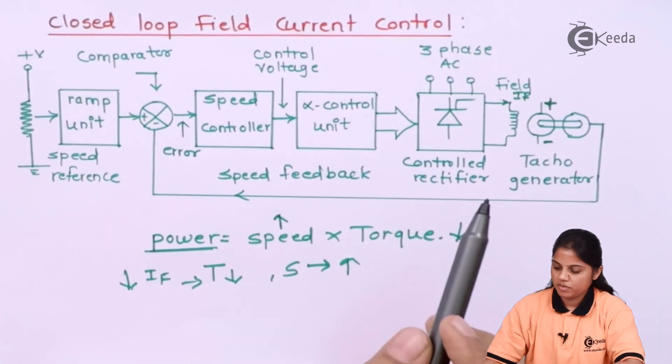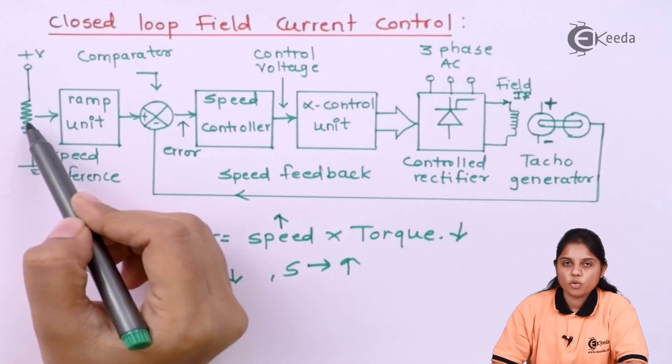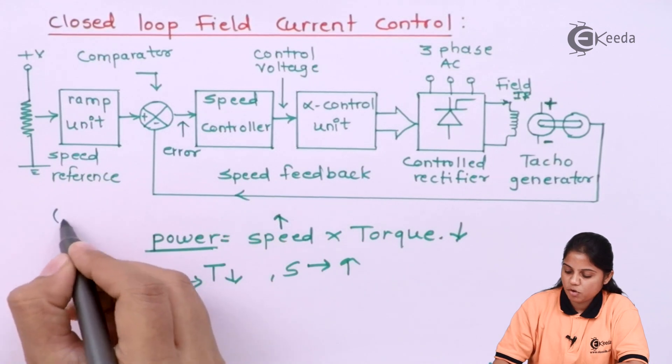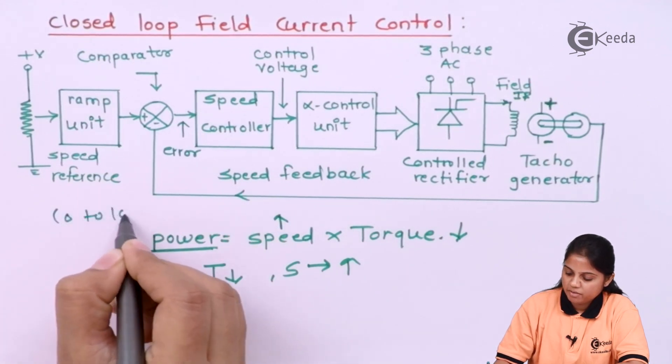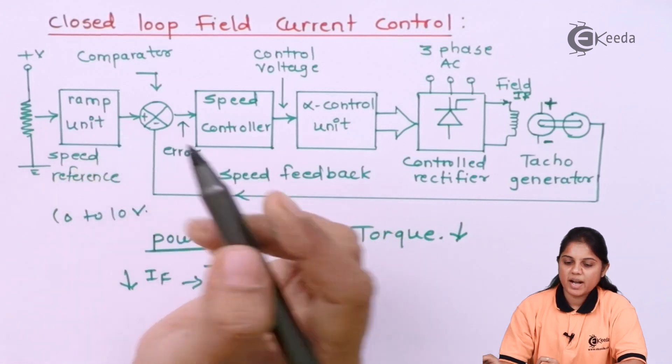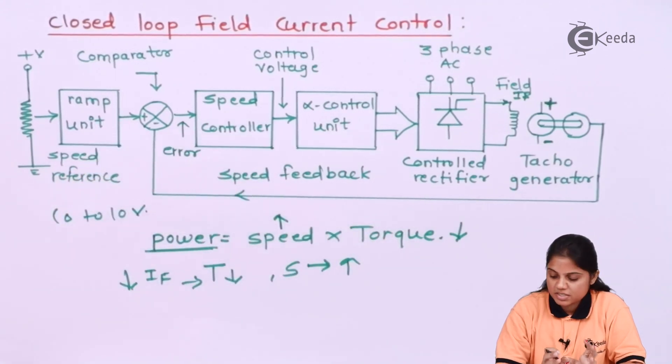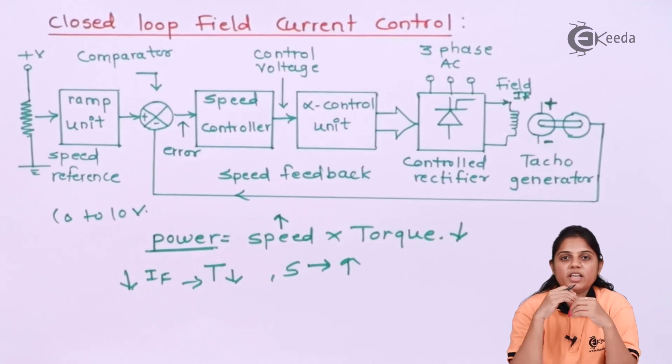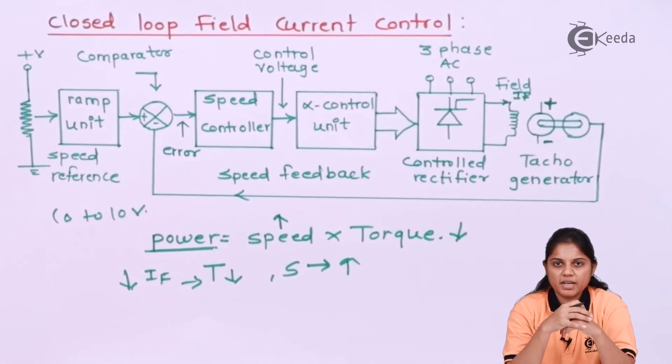Now let us see here what will happen. Again, you have a potentiometer where you have given a plus voltage and this voltage will be from 0 to 10 volts. This will be given to the ramp unit. So the ramp unit will give you soft start, and soft start is nothing but gradual acceleration of the motor.